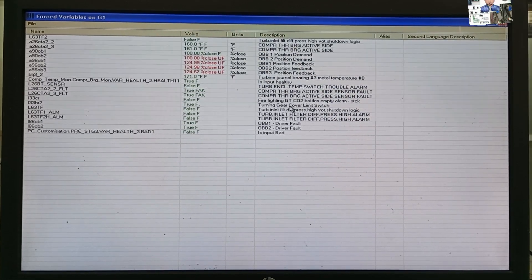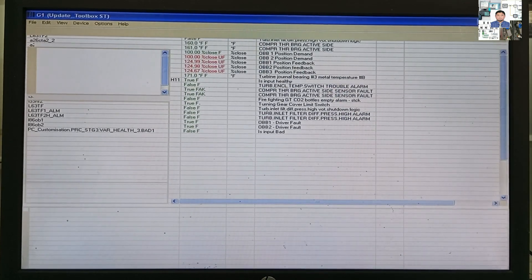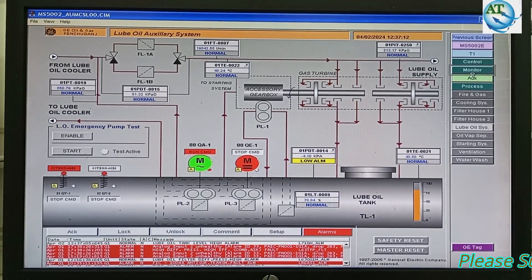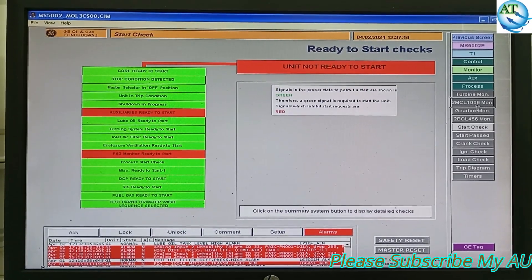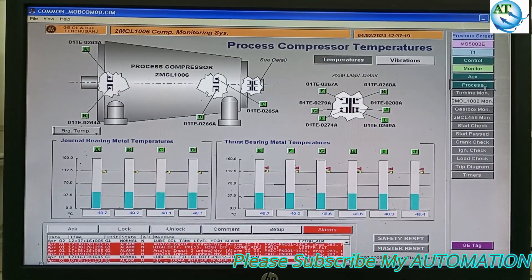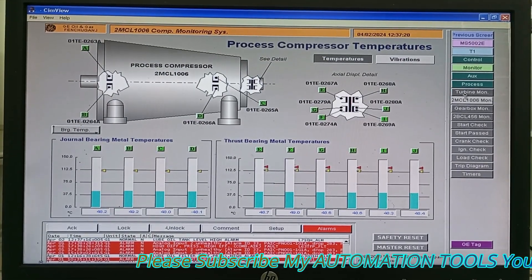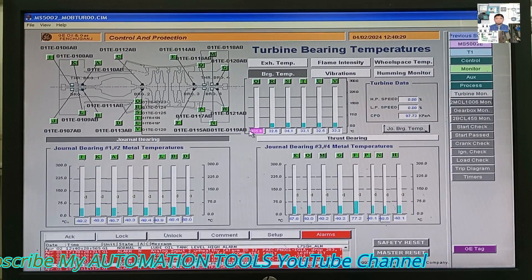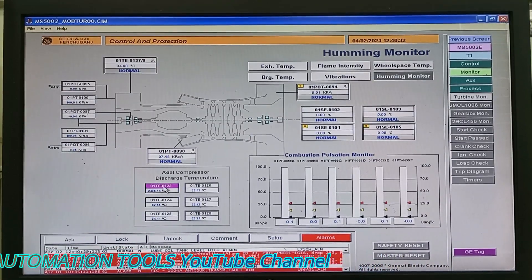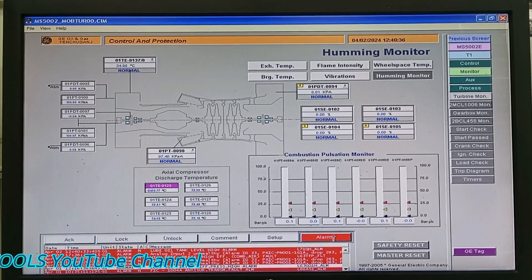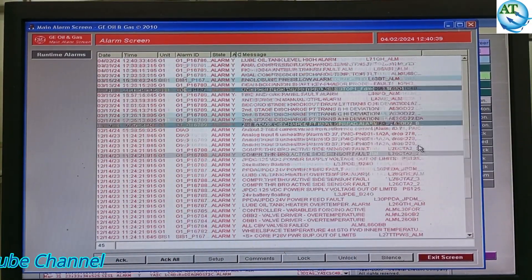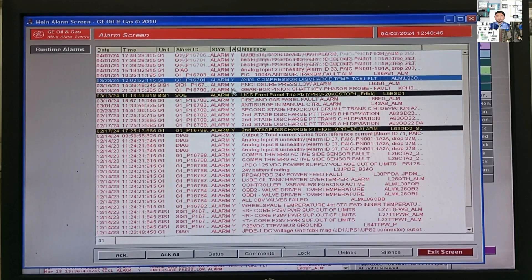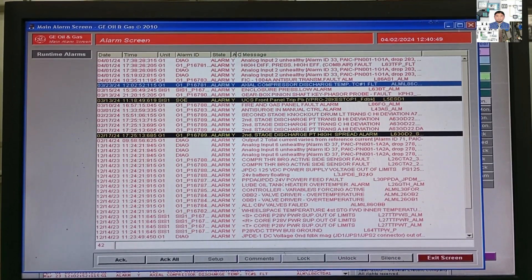For a defined purpose, we have to force a defined element under normal or changing conditions. I will show how we can force an analog or digital input value for maintenance purposes. I am finding one of the faulty instruments that we want to change or replace. Here, a faulty instrument is showing the wrong value — the temperature transmitter. Maybe the sensor of this transmitter is damaged. We want to repair this one. In the alarm system, we can see that this transmitter is showing an alarm: compressor discharge temperature sensor fault. So, we have to replace this sensor.